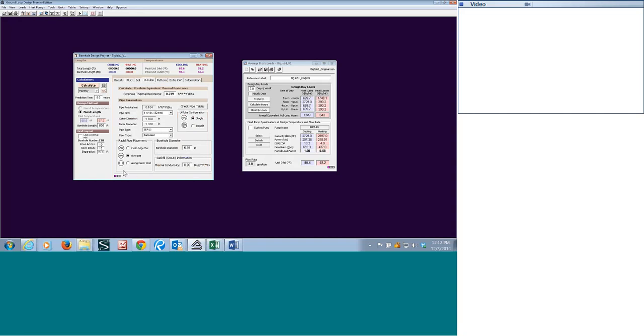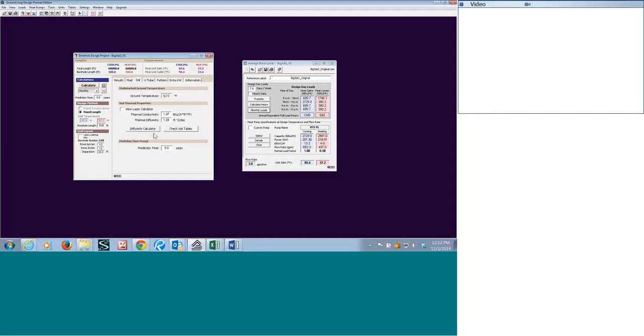Because geoclips were not used, or any other appliance to force the loop out to the sides of the borehole, we're going to use the average placement here. You can play with this, but you'll find that in most cases it'll make some difference, but when you look at using thermally enhanced grout versus clips and all, it may not make that much of a difference in a lot of cases. Our thermal conductivity test parameters provided an undisturbed ground temperature of 62 degrees. We had a thermal conductivity of 1.47, and the TC test report gave a diffusivity of 1.09.